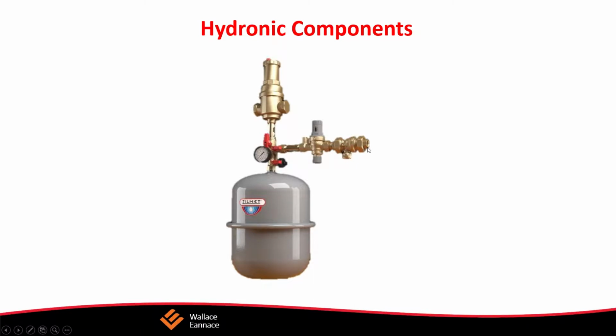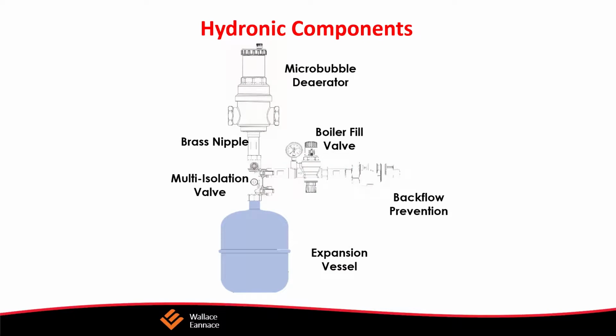You have to understand one thing: we're looking to absorb the expansion of water. So as I like to say, you can't have too much expansion tank. Expansion tanks relative to other components are not that expensive. When in doubt, you always want to go larger. It's not going to cost a great deal of money, and if you have to start changing things and going back, or it starts to blow relief valves, it's not worth the aggravation. The cost difference between a 30 and a 60 is not that much money. And these numbers here are very forgiving.